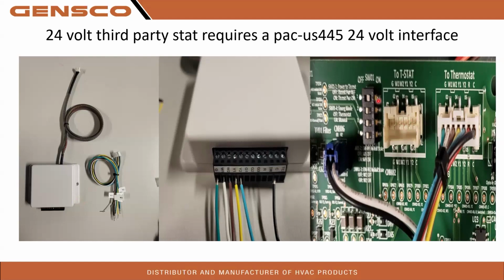On your relay board, you have a single dip switch bank called SW01. Do not mix this up with SW1 on the control board. So SW1 on the control board is model selection. SW01 on the relay board is for testing operation, and also make sure SW01 switch 1 right here is always on. This should be on from the factory.